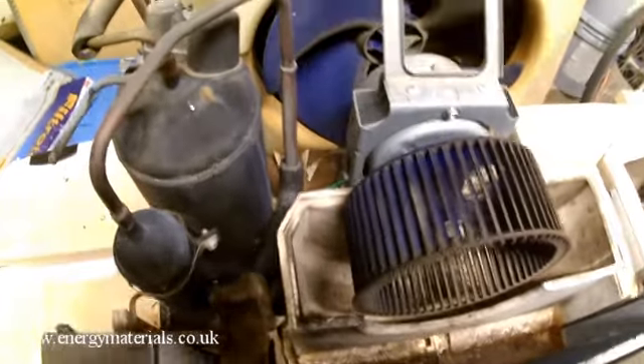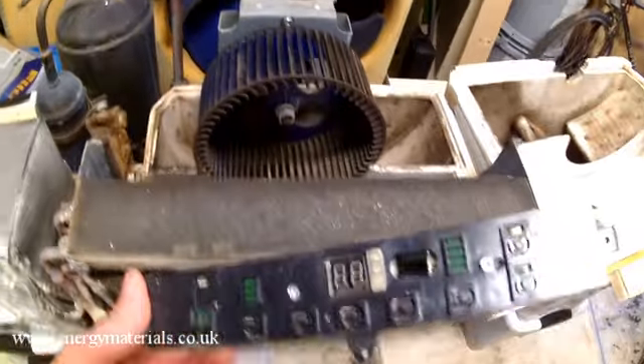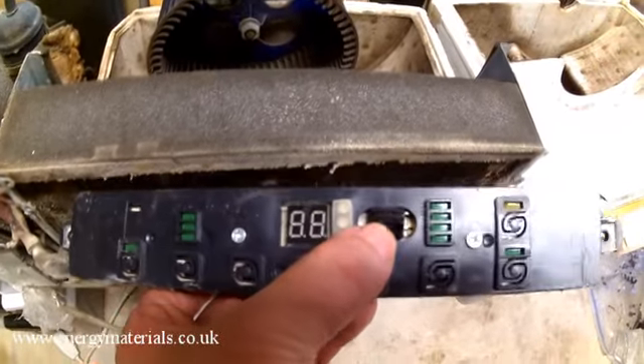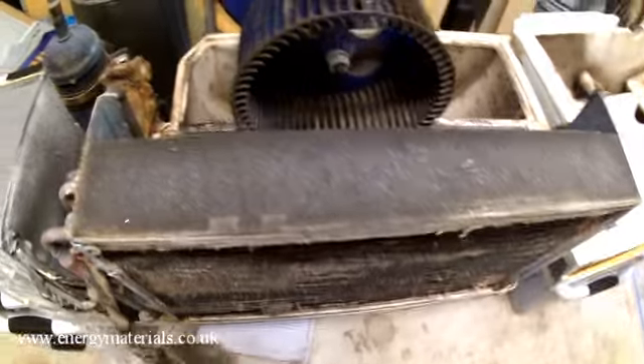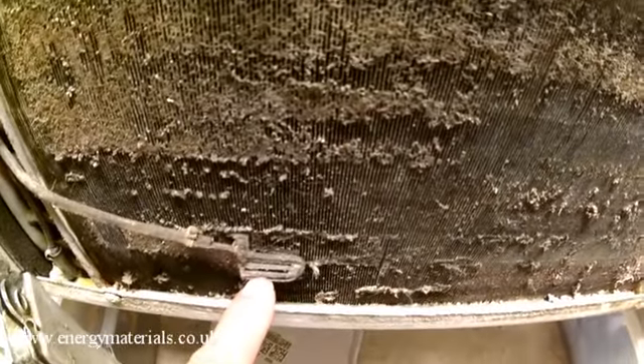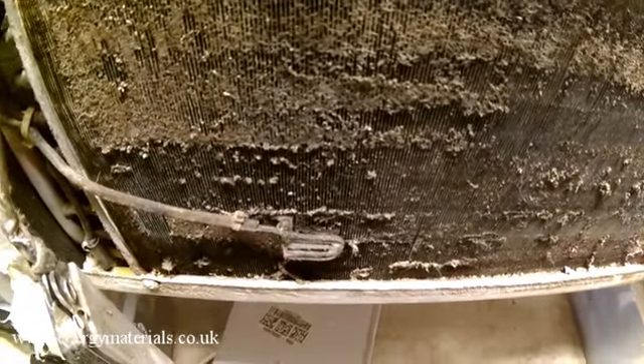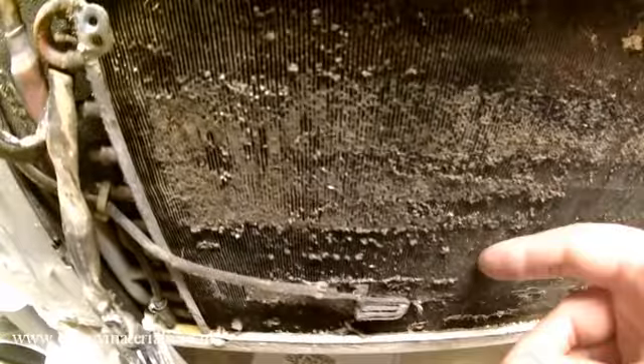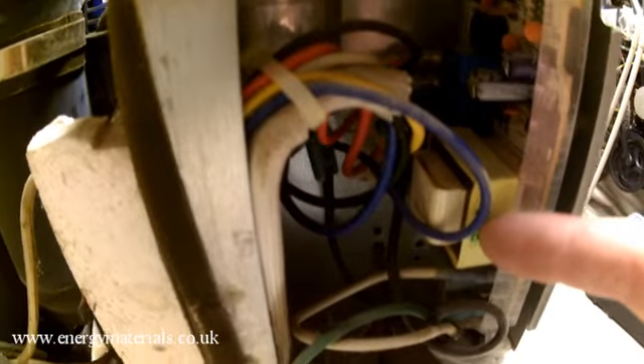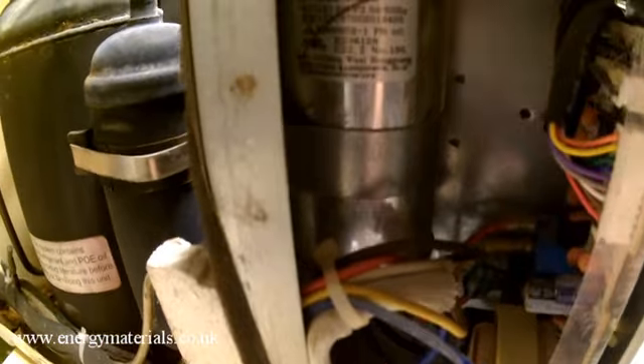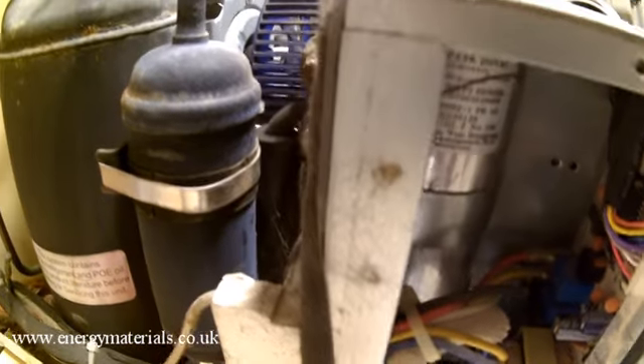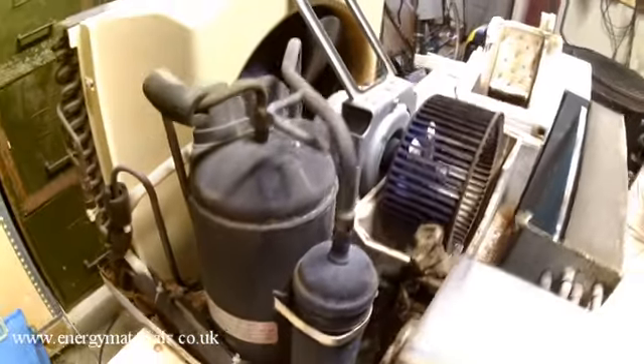So this particular unit's got a control system, nice basic one. So there's the control panel. Looks like here there's an IR sensor, so it must have been fitted with a remote control. There appears to be a thermocouple on the front of the system for measuring the room temperature of the air going in. Maybe also to measure the temperature of the heat exchanger to avoid freezing. And there's a control system, very simple, little control transformer, starting capacitor, probably for the compressor motor. Two relays, these are the blue units. These relays are contactors, would have electrical switches, probably one for the compressor and one for the blower motor.